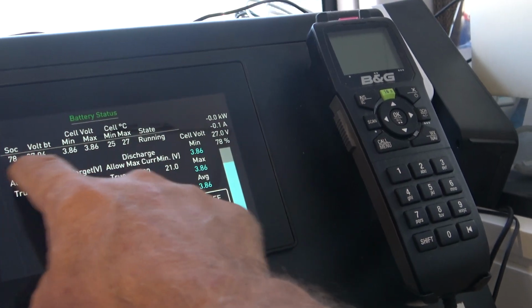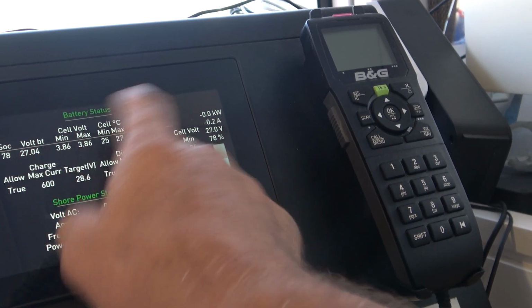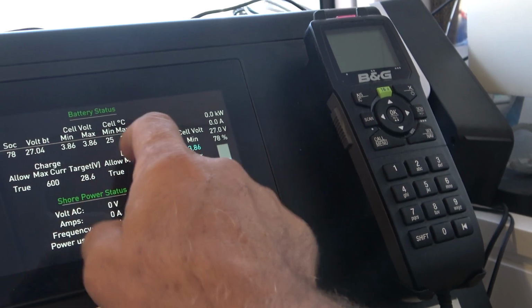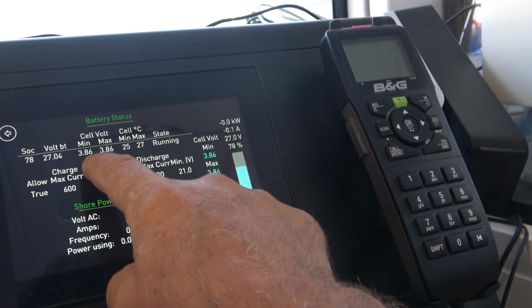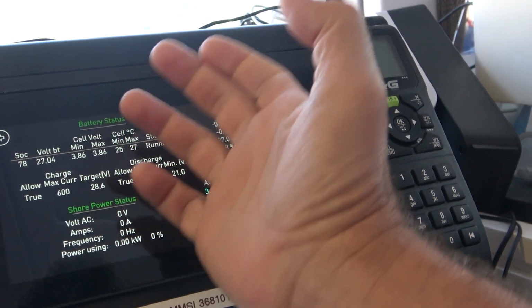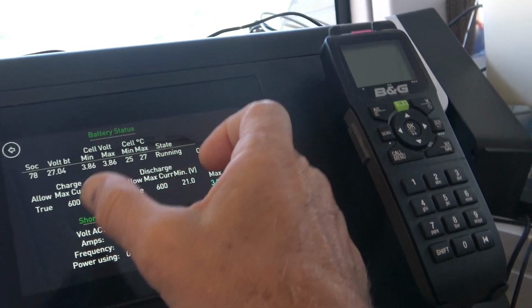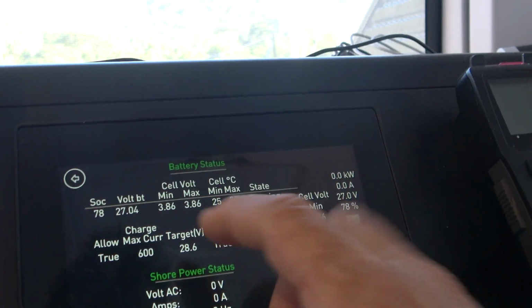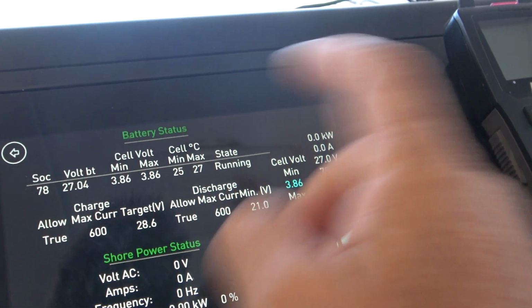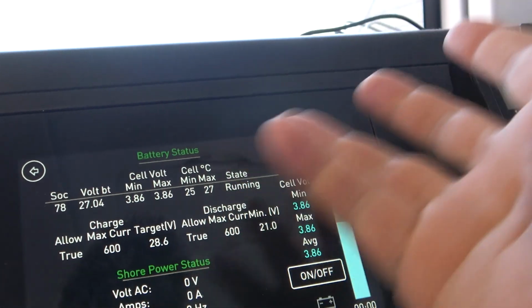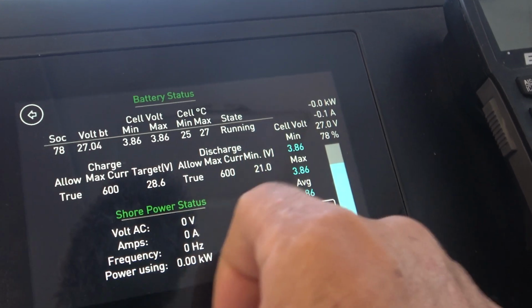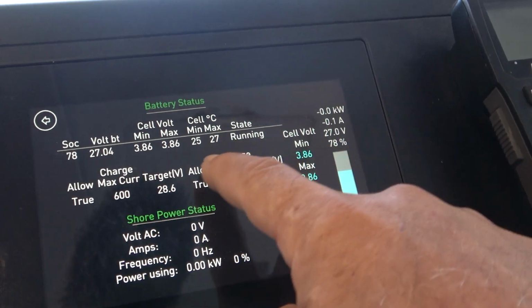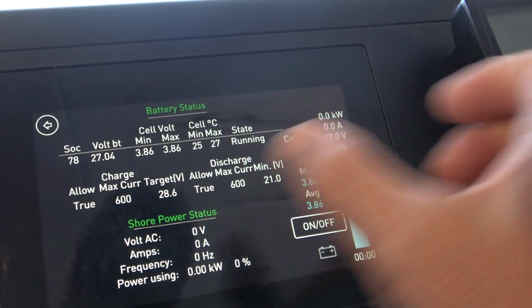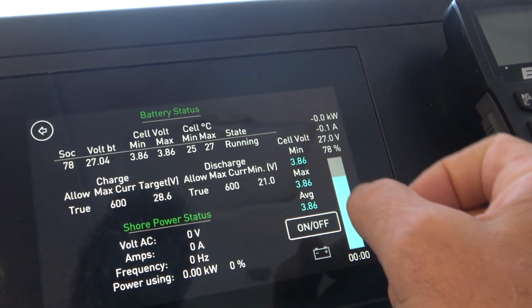Then you go down to the cell level. Right now the state of charge is at 78%. The voltage of the whole battery is at 27.04 volts, which corresponds to 78% state of charge. Then we see the minimum and maximum cell values. You have 3 batteries in parallel right now, and each battery has 7 cell blocks, built with 3.65 nominal battery cells. And the minimum and maximum temperature — these two temperature probes are in different places in the battery box, so that small difference is normal.